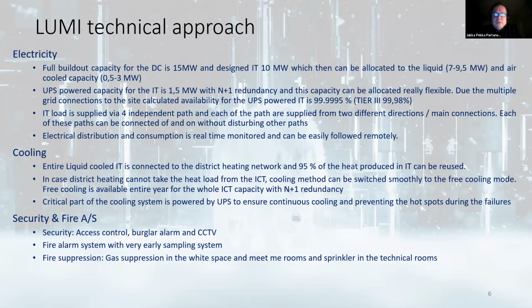And the critical part of the cooling system is powered by UPS. Then for security and fire, security access control, burglar alarm and CCTV are installed, and fire alarm systems are very early sampling systems. And for fire suppression, we use gas, or we planned it at that time, and of course we implemented it. So gas suppression in the white space and meet-me rooms, and then sprinklers in the technical rooms. So those were the design principles when we started the data center project.